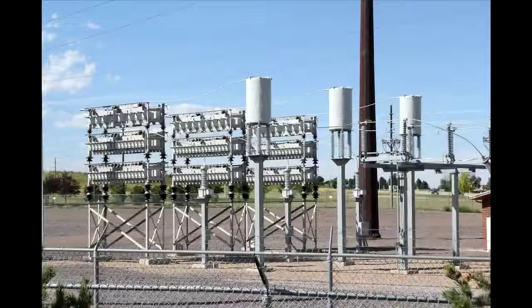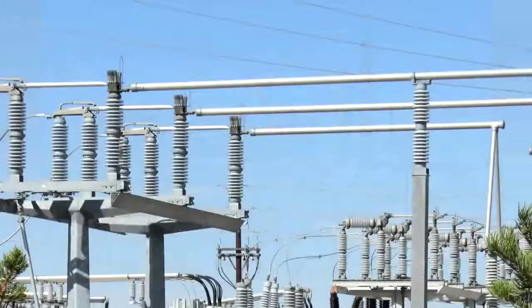And, one got a little excited about it until you realize that a 3-phase line, when it goes into the substation, has 3 circuit breakers to open it, close it. And throughout that substation, there are 3 bus bars that these connect to. With a 6-phase line, there would be 6 circuit breakers and 6 bus bars. 12 phases, there would be 12 circuit breakers and 12 bus bars.